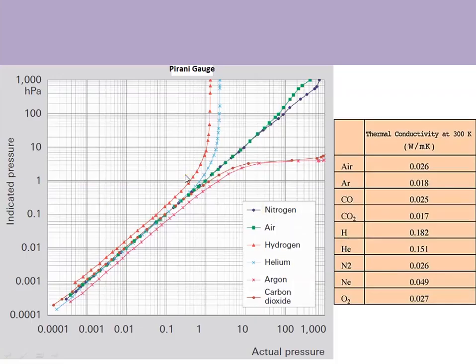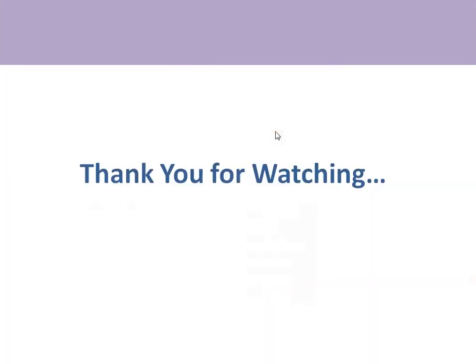The Pirani gauge is gas-dependent. If a gauge calibrated for air is used for argon, which has lower thermal conductivity than air, the gauge will show lower pressure values even when actual pressure is higher, because less heat is transferred by argon. Conversely, if used for helium, which has higher thermal conductivity, the gauge will show higher pressure even when actual pressure is lower. Therefore, the gauge must be calibrated for the specific gas being measured, as each gas has a different thermal conductivity value.